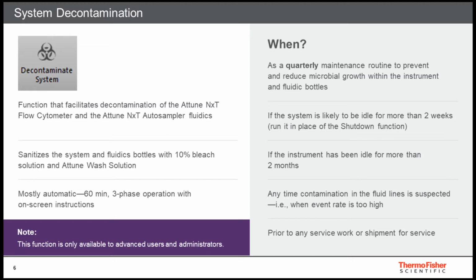It is extremely crucial that you do not initiate the system decontamination script unless 2 replacement Attune NxT focusing filters are available on hand. As in the first phase, 10% bleach solution is run through the system, destroying the filters. Leaving old filters on after the decontamination script may cause filters to tear off gradually and ultimately clog the system, which may require serious intervention in order to clean and continue. The decontamination script, much like other Attune NxT fluidic function scripts, is quite descriptive and walks the user through the process. Please follow the instructions on the screen through the 3 phases.